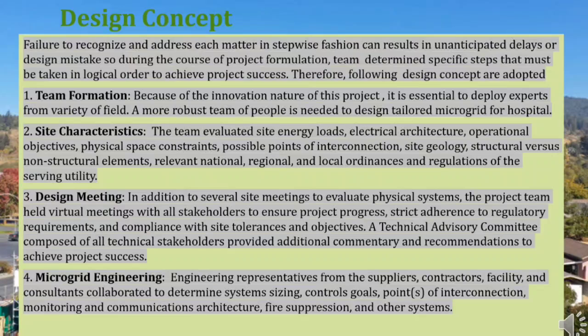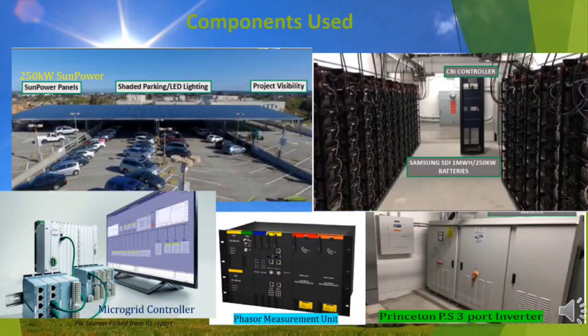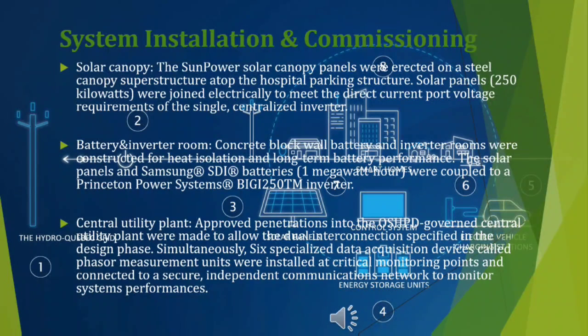Next, we have microgrid engineering. Engineering representatives from the supplier, contractors, facility and consultants collaborated to determine system sizing, control goals, point of interconnection, monitoring, communication architecture, fire suppression and other systems. The components used in this project are a 250 kilowatt solar array, 1 megawatt-hour Samsung batteries, phasor measurement units, and a Princeton Power Systems three-port inverter.